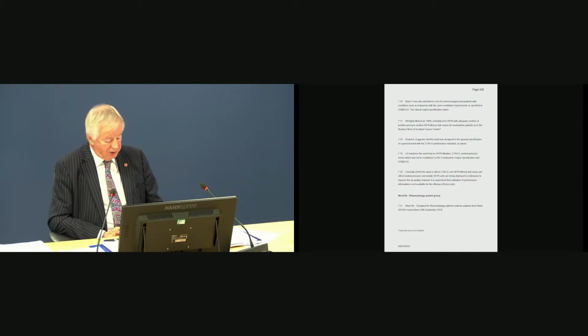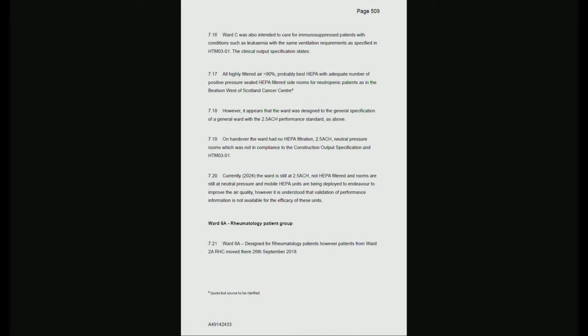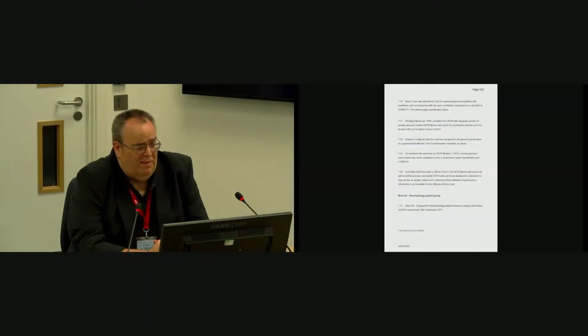On 7.20 you say this ward is still at 2.5 air changes, not HEPA filtered, rooms at neutral pressure. Just pausing there - from your perspective, is that a satisfactory situation or not? In my experience, I would not expect that to be used for this patient group without significant other mitigation deployed to address it. But again, this is really a question for a multidisciplinary group to answer rather than myself purely from a ventilation perspective.